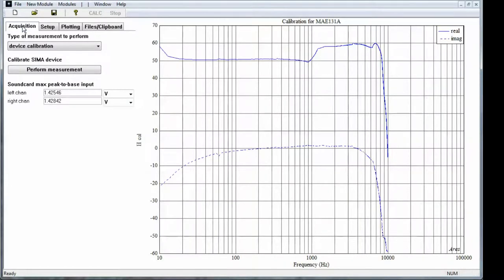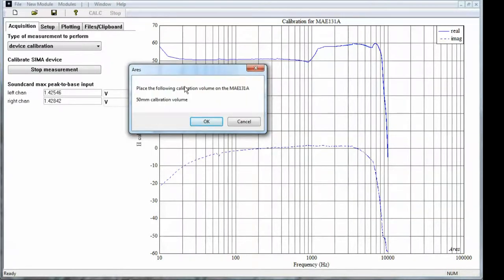Next, we'll go to the acquisition tab. There are two acquisitions that can be performed. One is a device calibration and the other is the actual impedance measurement. We're going to go ahead and do a device calibration just to show how it's done. So we've got the 131 selected already and set up. We're going to hit perform measurement. ARES will communicate with electronics and then ask you to place the 50mm calibration volume on the 131.